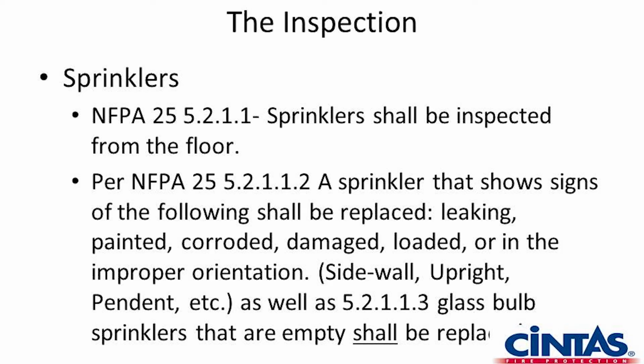It seems kind of crazy to think about a sprinkler being installed in the wrong orientation, but we have replaced a sprinkler that was designed to be in an upright position, with the water going up, hitting the deflector, and having its umbrella come down, that was installed in a pendant position. What that's actually doing is the water is now shooting down and the spray pattern is going up, so we're not getting that coverage umbrella that we're looking for.